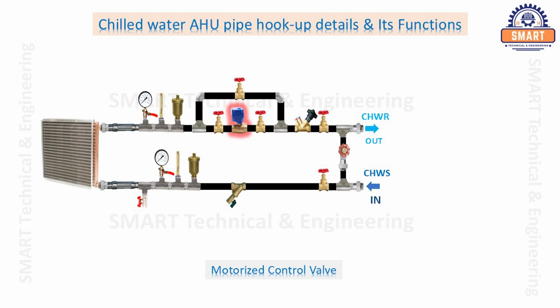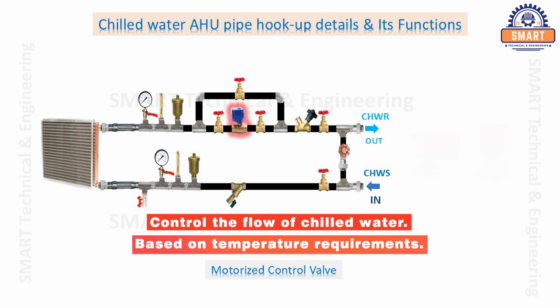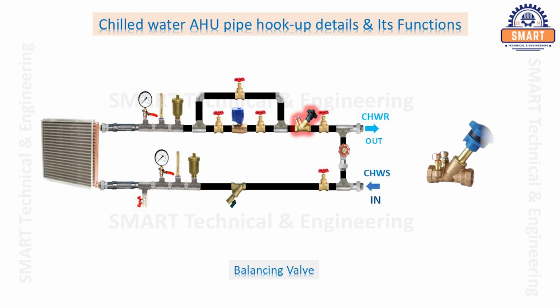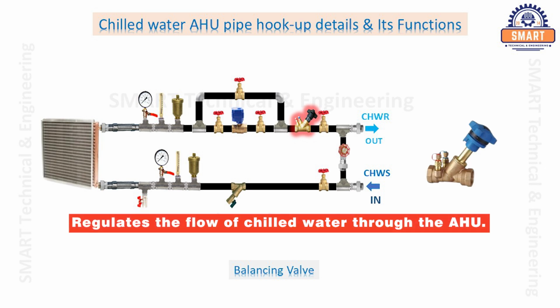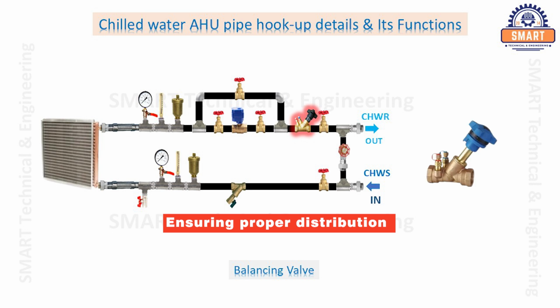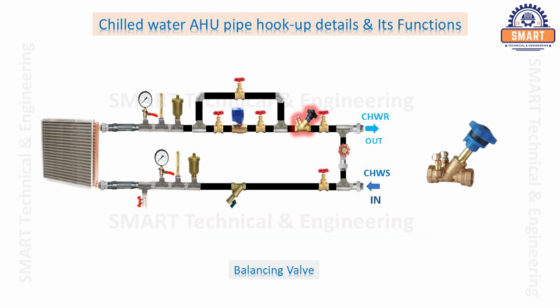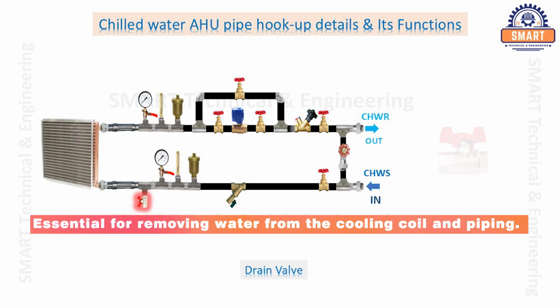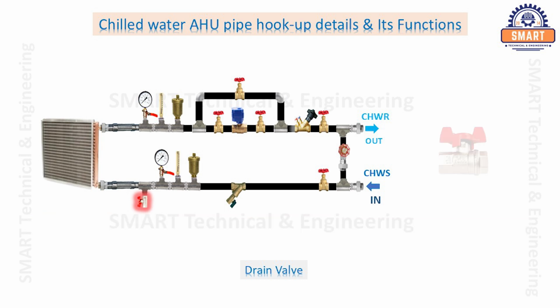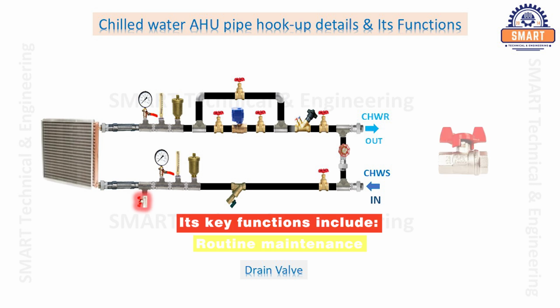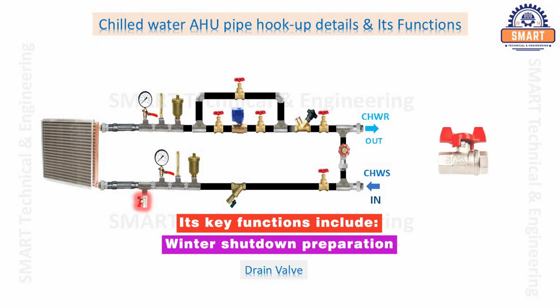Motorized control valve. Motorized two-way or three-way valves control the flow of chilled water based on temperature requirements. Balancing valve. This valve regulates the flow of chilled water through the AHU, ensuring proper distribution and preventing imbalances in the system. Drain valve. The drain valve is essential for removing water from the cooling coil and piping. Its key functions include routine maintenance, coil replacement, winter shutdown preparation, and pressure testing.